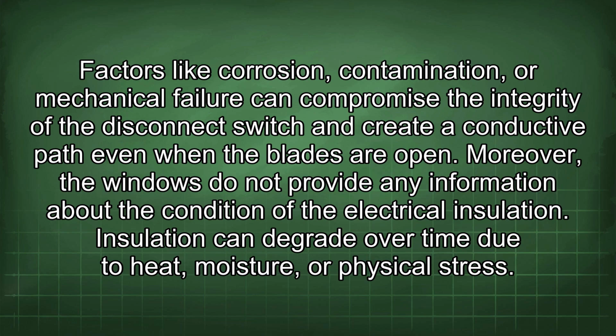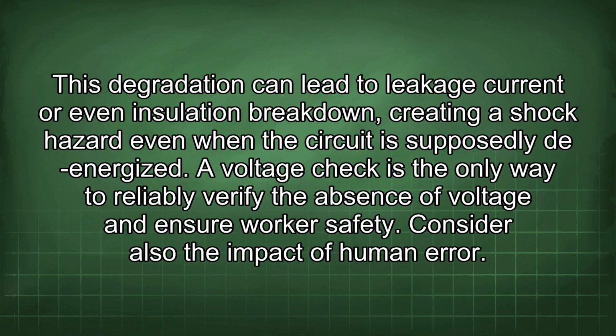Moreover, the windows do not provide any information about the condition of the electrical insulation. Insulation can degrade over time due to heat, moisture, or physical stress. This degradation can lead to leakage current or even insulation breakdown, creating a shock hazard even when the circuit is supposedly de-energized. A voltage check is the only way to reliably verify the absence of voltage and ensure worker safety.